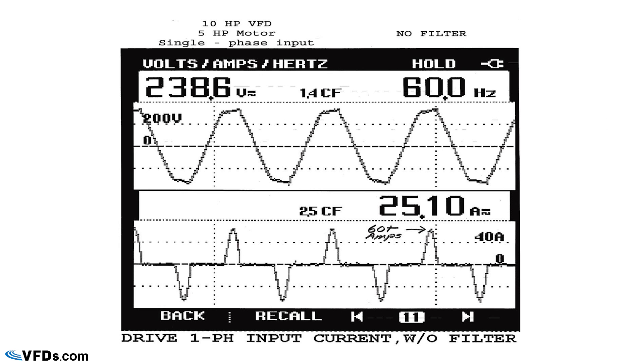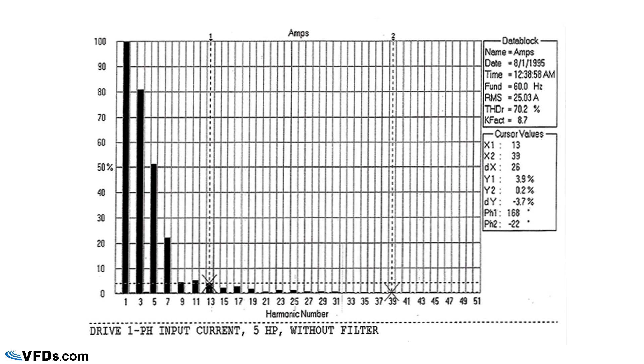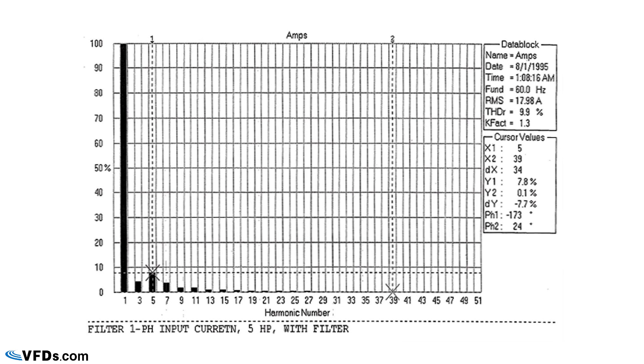Now you don't really need to understand how those filters work; you simply need to understand that they work. Let's take a look at an actual installation. This is in our shop — a 5 horsepower motor — and you can see that the current on the bottom is taking power in short pulses, and it's causing extensive flat topping. Putting a filter on this has a dramatic effect, and you can see that the current is not exactly a sine wave but very close, and the voltage has been corrected to a virtually perfect sine wave. If we look at this on a harmonics meter, you can see that the first harmonic is 100% — that's the good one. All the rest of them are bad ones, and we have significant harmonic pollution. By putting a filter on, the first harmonic is still 100%, but we've dramatically reduced the harmonic pollution on the remainder of these high-frequency noise signals.